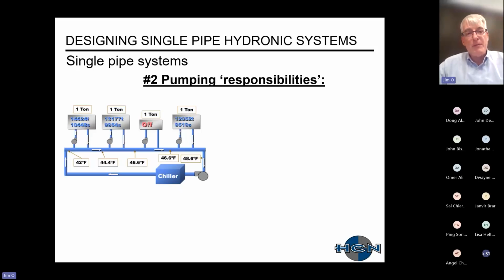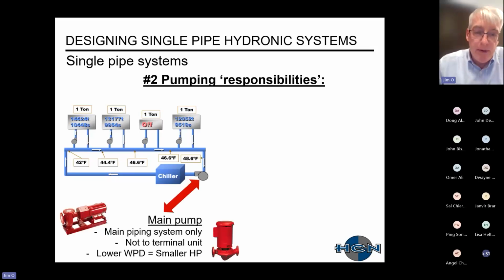Now, in terms of pumping responsibilities, you have 2 pumps. You have a main circulating pump and then that little small circulator on the branch piping. So your main pump is doing the main piping system only. It's not going to the terminal units. And because you have a lower water pressure drop, you end up with a smaller horsepower, hence why you should save energy. That's depicting where the main pump is circulating the water.